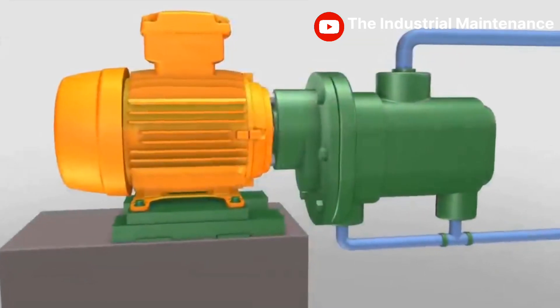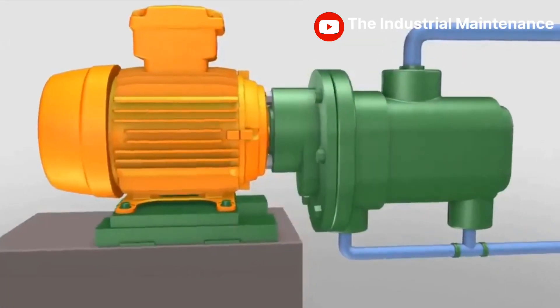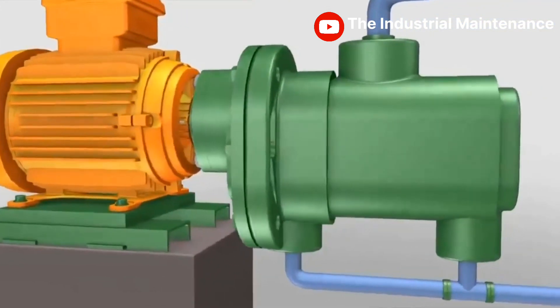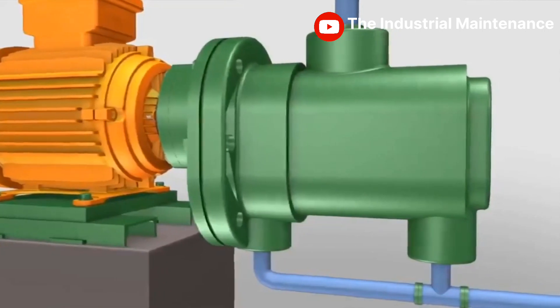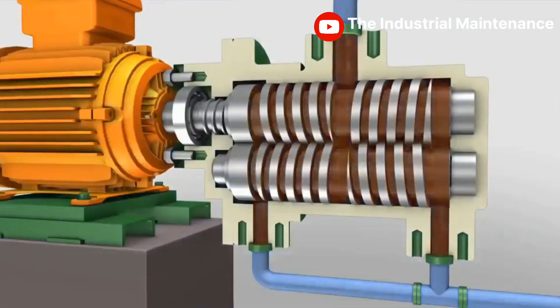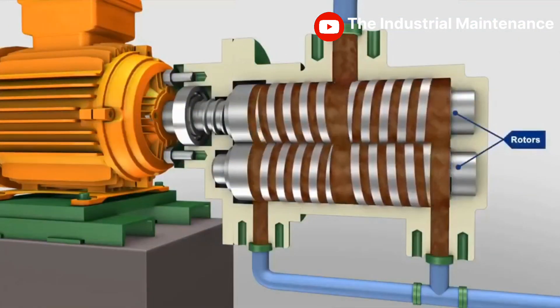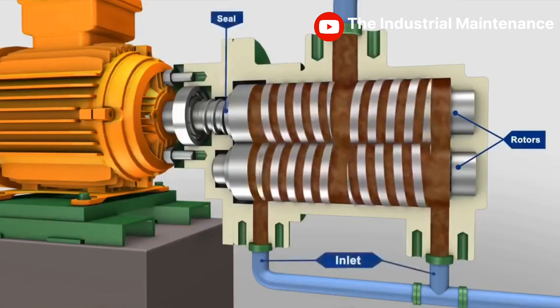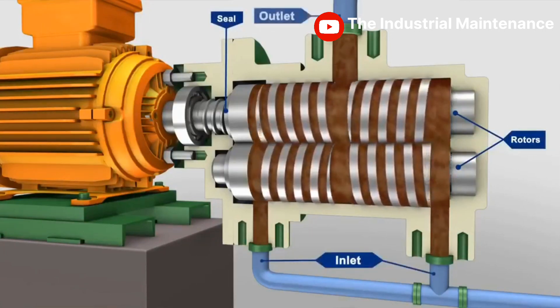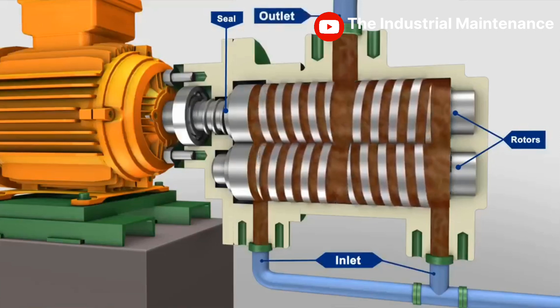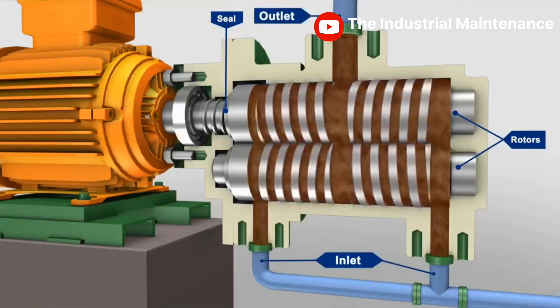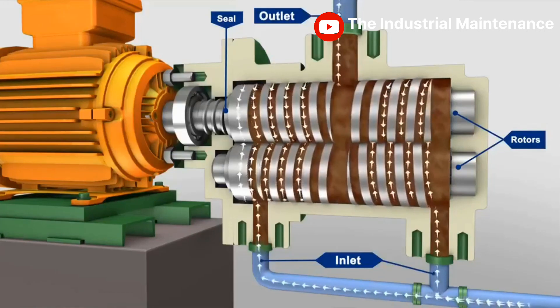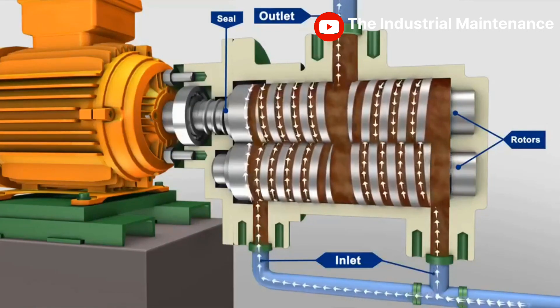In screw pumps, it is the intermeshing of the threads on the rotors and the close fit of the surrounding housing that creates one or more sets of moving seals in a series between the pump inlet and outlet. These sets of seals, or locks as they are sometimes referred to, act as a labyrinth and provide the screw pump with its positive pressure capability.